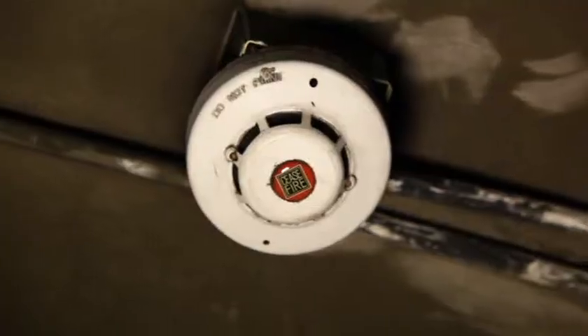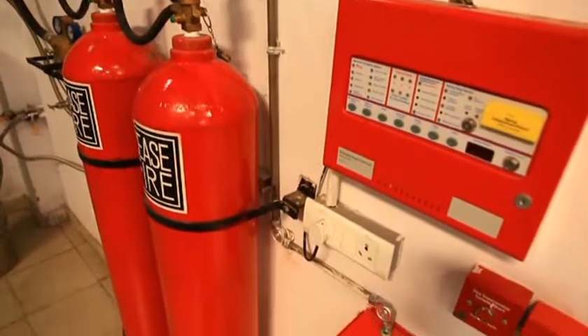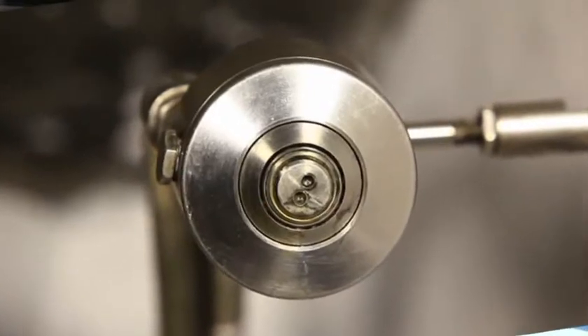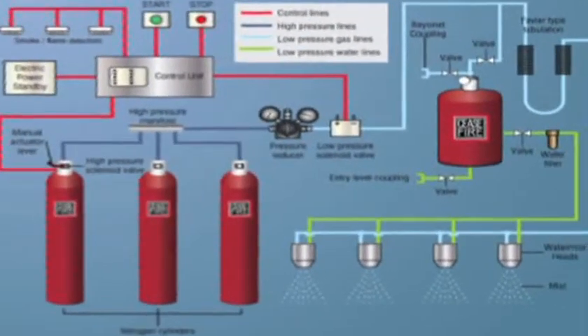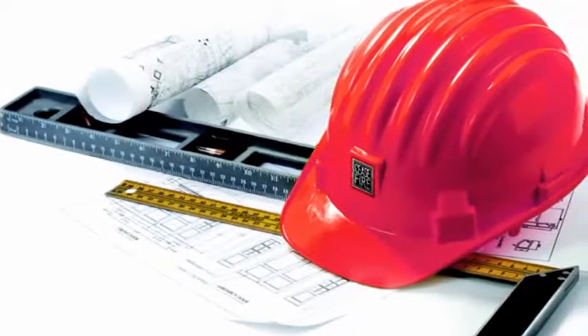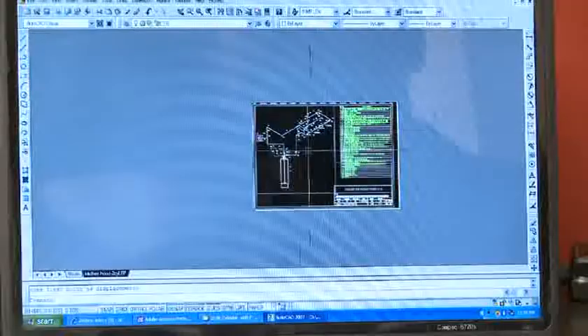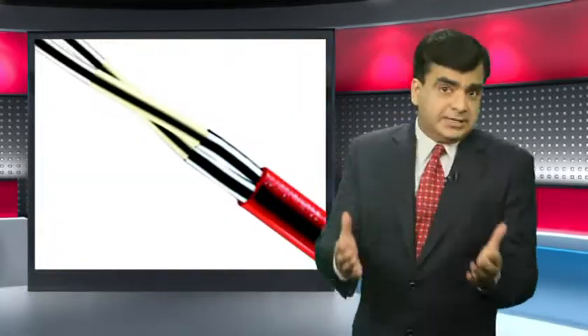The Dry Mist Total Flooding System is made up of detectors, control panel, pipes and fittings, water tank, air or nitrogen cylinders, and water mist nozzles. Do keep in mind that the system is designed by the Ceasefire design cell after studying the area's needs and vulnerabilities, so the setup will vary from premise to premise. Here are the smoke and heat detectors that raise the alarm when there's a fire. The detectors include either smoke detectors, heat detectors, and rate of rise detectors, or a combination of these. It can also feature linear heat detection.